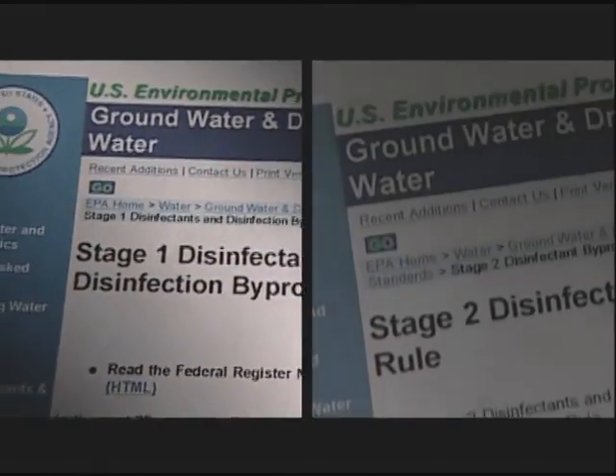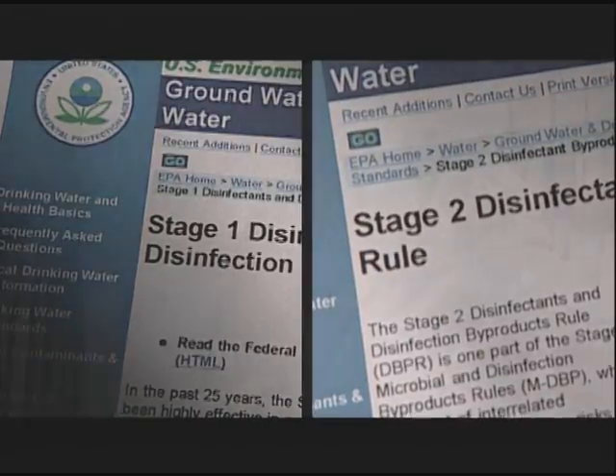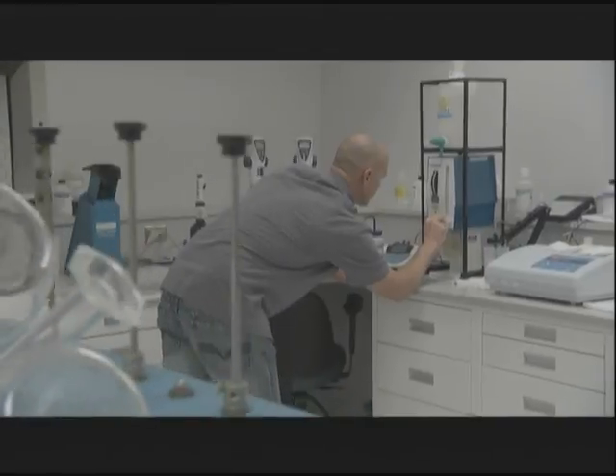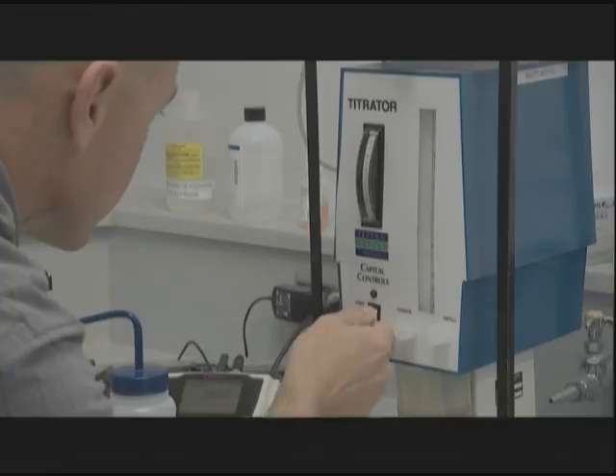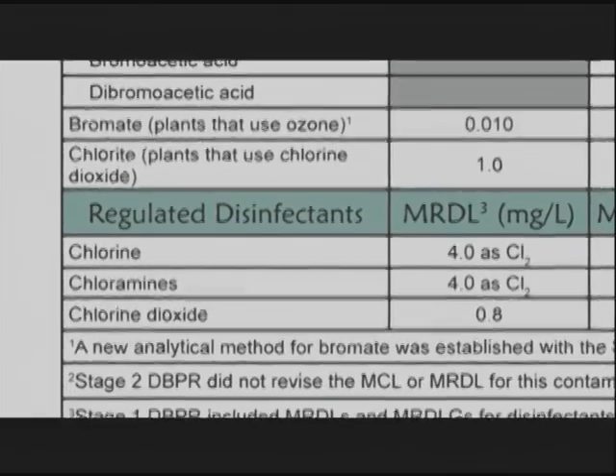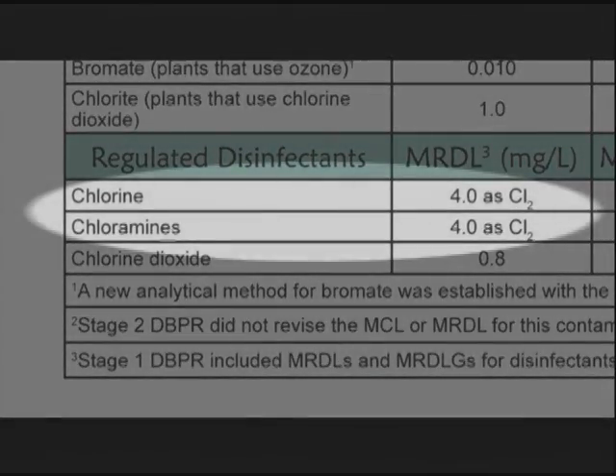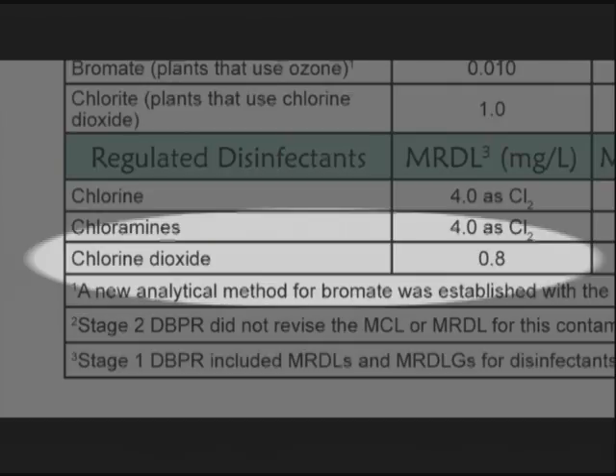The Stage 1 and Stage 2 disinfectants and disinfection byproducts rules also set a maximum residual disinfection level, or MRDL, for chlorine, chloramines, and chlorine dioxide. For both chlorine and chloramines, the maximum residual is 4 milligrams per liter. For chlorine dioxide, 0.8 milligrams per liter, or 800 parts per billion.